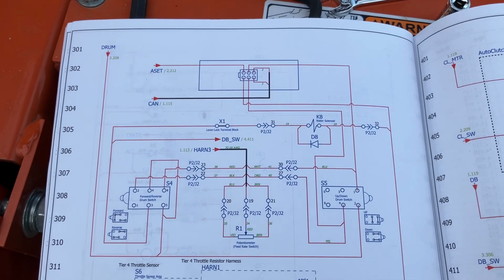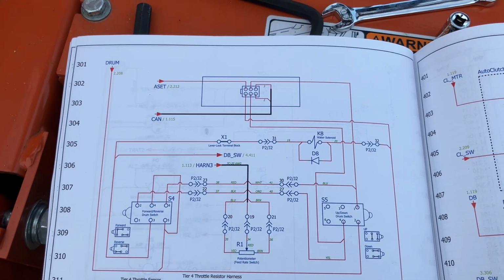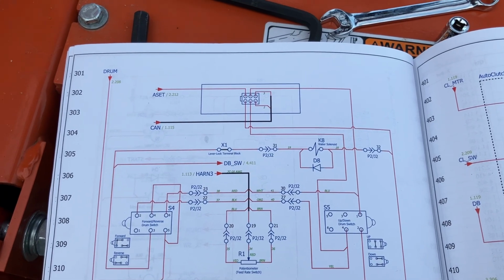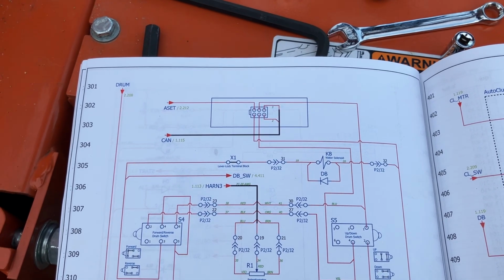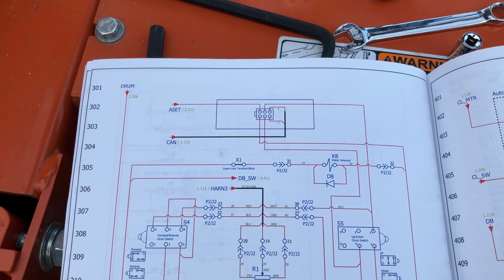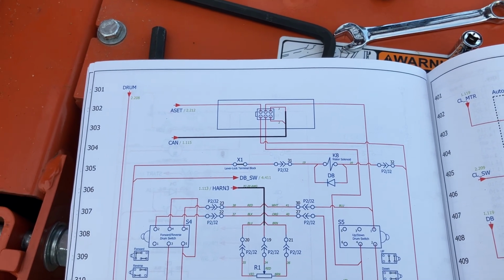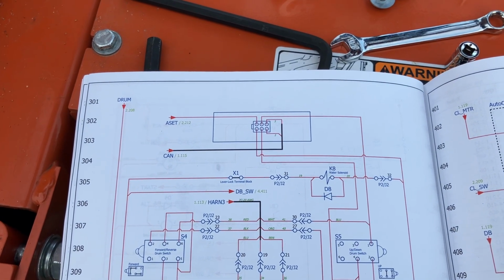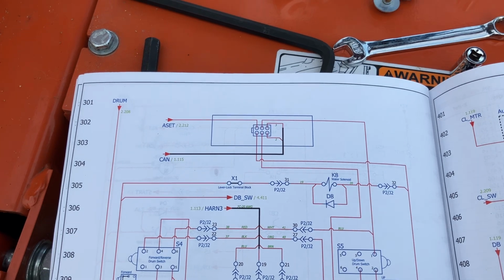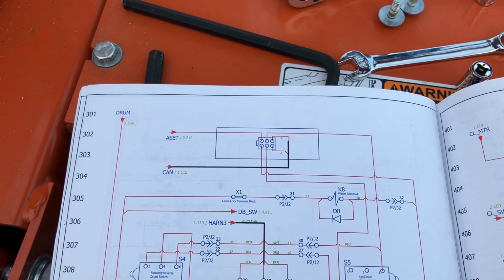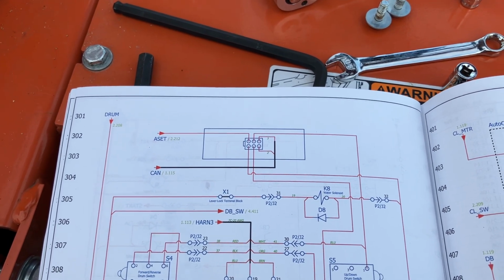go forward. So the issue ended up being the linear encoder was failed internally, which the power 24 volts must have been shorted to ground internally, which was drawing the system voltage down. So we're going to go through a little bit here on how we determine that.